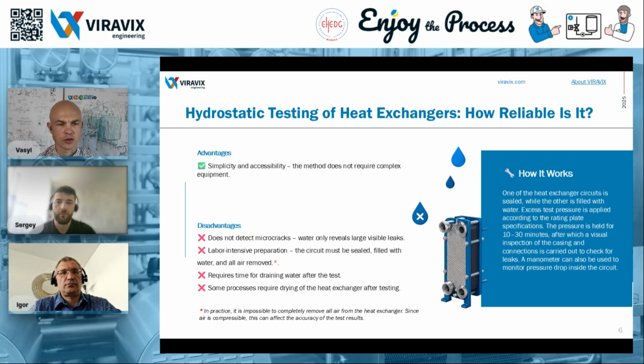Well, cracks that may or may not be detected by a hydraulic test can pose serious risks. Igor, based on your experience, and Sergey, I'd appreciate it if you could share your thoughts as well. What types of cracks does this method usually fail to detect, and why might that be the case? According to the claims of suppliers who provide hydraulic testing services, this method is capable of detecting cracks with an equivalent size of approximately 50 microns or larger, meaning only relatively large defects. I say equivalent because, for comparison, they use perfectly round holes, which don't actually occur in real heat exchangers. So I prefer to say equivalent size rather than exact size.